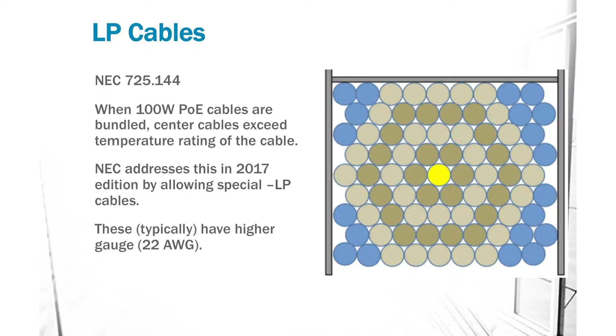And they logically applied the thought process that when you're pumping 100 watts down a category cable that's just routed in your plenum space, not in conduit, there could potentially be issues, right? So they went out to UL and they did testing on a variety of cables that are 22, 23, 24 gauge. I think they did 25, 26 as well, some of the niche manufacturers. And those cables are tested to certain temperatures, just like the power conductors. So usually it's 60 degrees Celsius, 75, and 90 degrees Celsius.